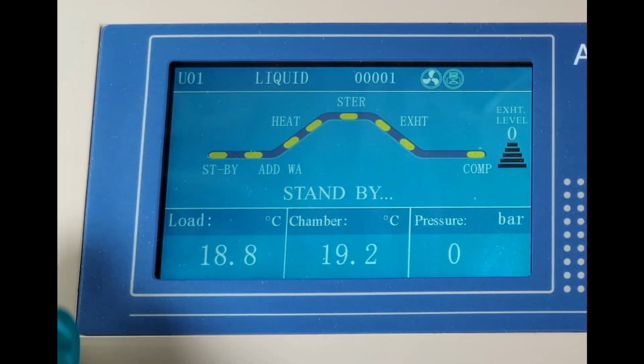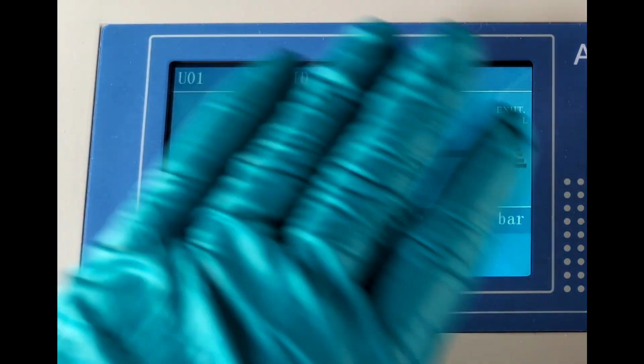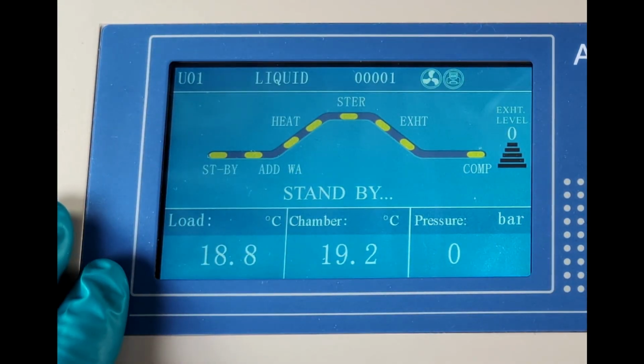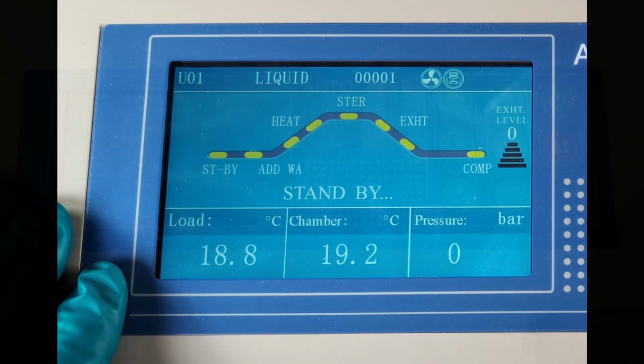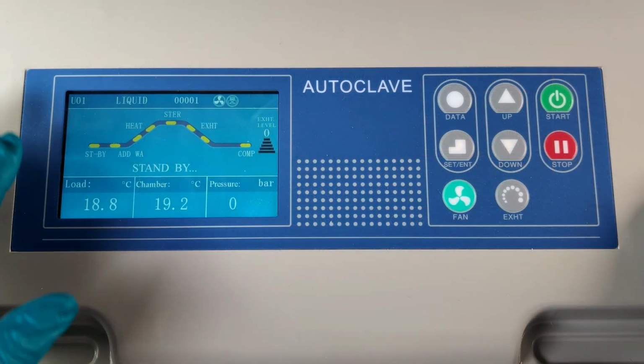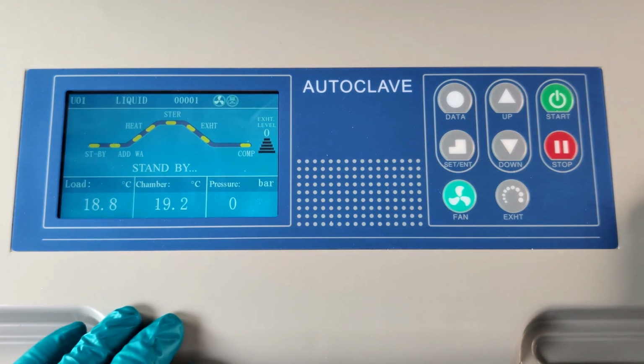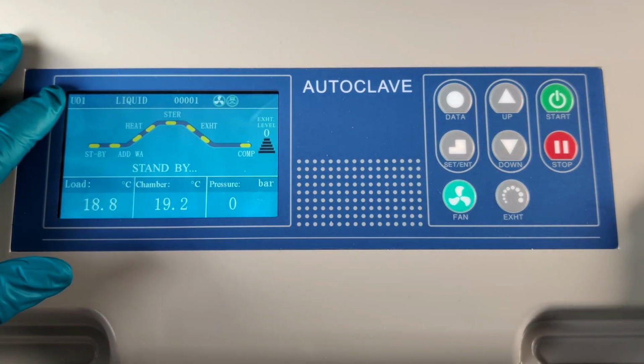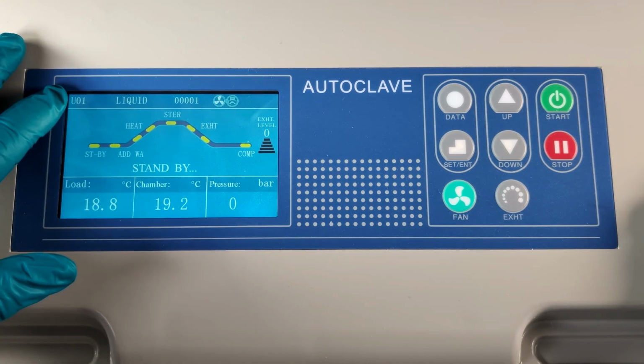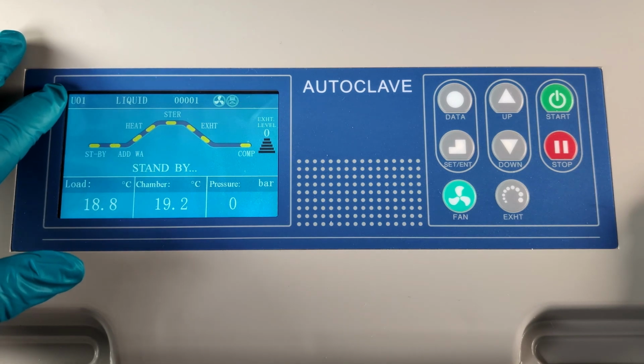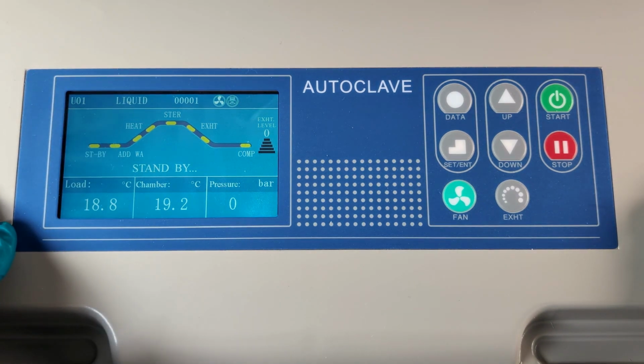But let's have a look at the screen on the left in particular. It's a very clear screen which also shows you a lot of detail both about the autoclave status, what program it's running, and how the cycle is progressing. So let's start with the top left-hand corner and work our way through. First of all, you'll see the user program number, in this case user program number 1. The autoclave comes preloaded with 10 programs, but if for some reason that's not enough, you can do your own programs, up to 60 of them.